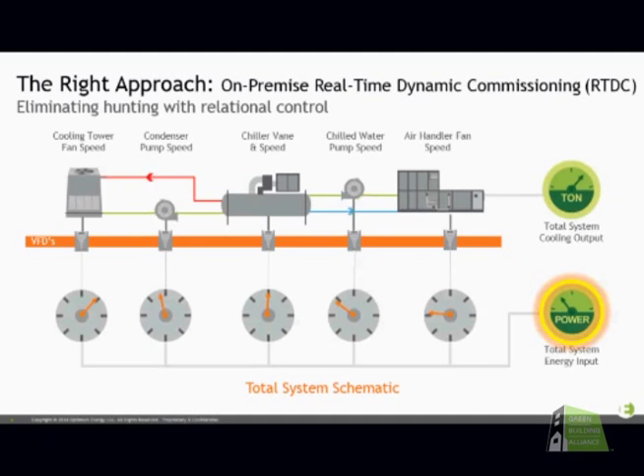So what we often see is about a 4-hour threshold. If you're pulling in data and looking closely at it, you can map out exactly when that's going to happen and run more efficiently. The problem is operators in a real plant are running around trying to do maintenance, repair things, and operate the plant. They're not going to be looking at the weather every hour, seeing what the forecast is for the next 4 hours. So that's just a little deeper explanation of that.